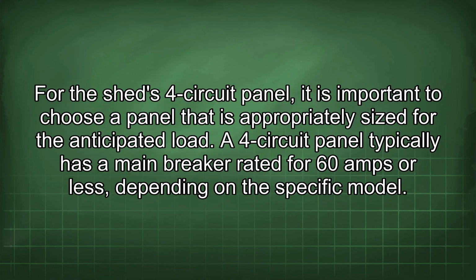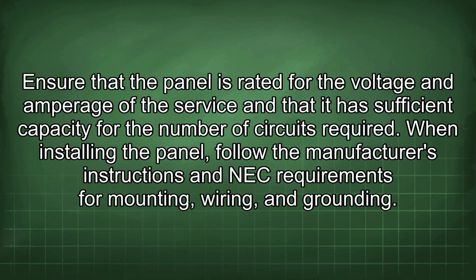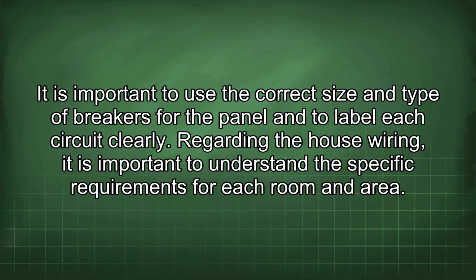For the shed's 4-circuit panel, it is important to choose a panel that is appropriately sized for the anticipated load. A 4-circuit panel typically has a main breaker rated for 60 amps or less, depending on the specific model. Ensure that the panel is rated for the voltage and amperage of the service and that it has sufficient capacity for the number of circuits required. When installing the panel, follow the manufacturer's instructions and NEC requirements for mounting, wiring, and grounding. It is important to use the correct size and type of breakers for the panel and to label each circuit clearly.